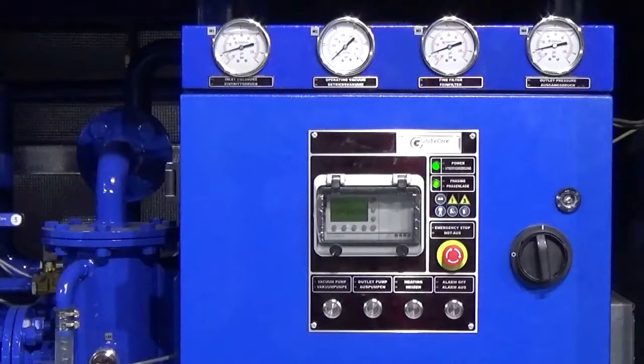Correct phasing is indicated by the green light on the phase control relay and the phasing light on the front panel of the control cabinet. If the power light is on while the phasing light is not, check phase control relay settings and, if necessary, swap connections of phases on the input terminals of the phase connector. Turn the power connector handle on to the on position.